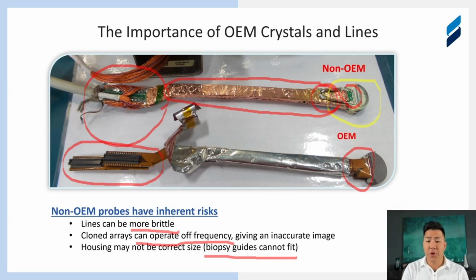And so we just wanted to take a moment to share that the criticality of the performance of the equipment is in the crystal and the lines, and it is imperative that when you're getting your probes repaired and serviced, you make sure that it has the OEM crystals and lines in there.